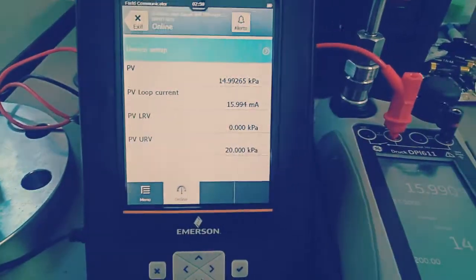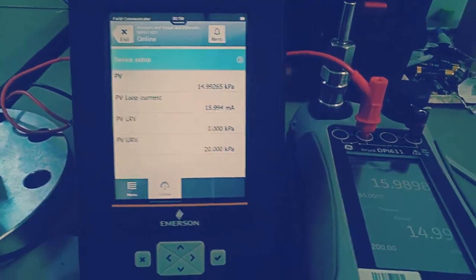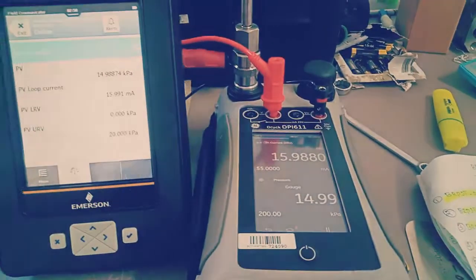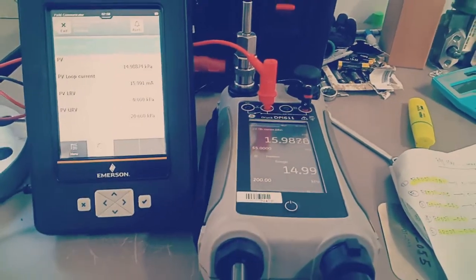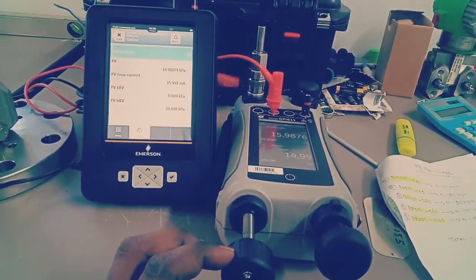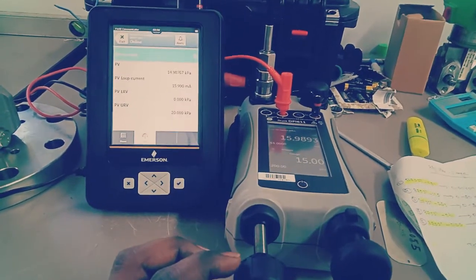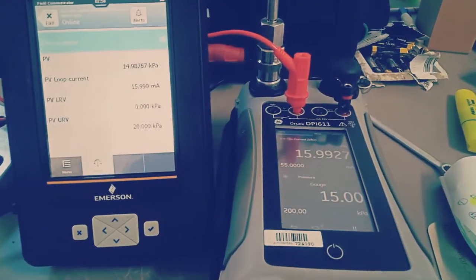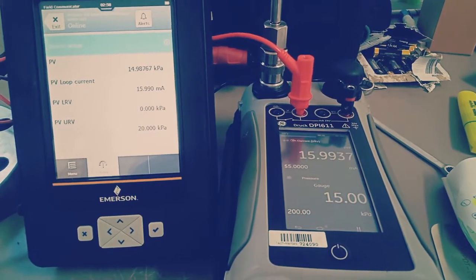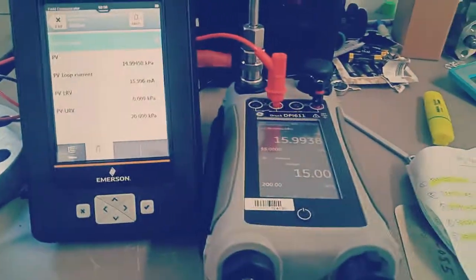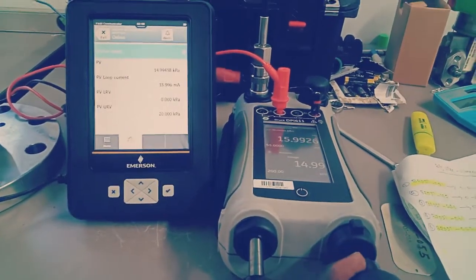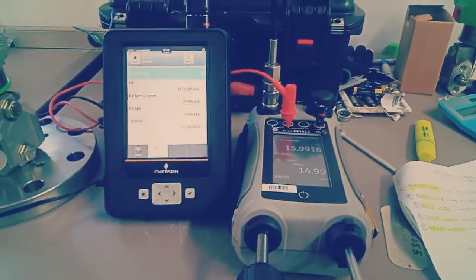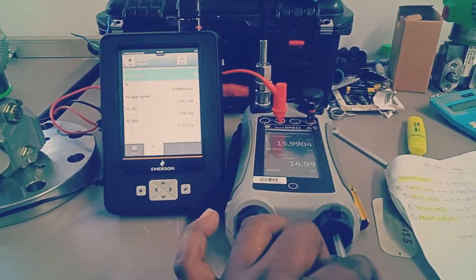It is acceptable according to error calculation and transmitter error limit. You can see it reads for 15 kilopascal, it reads almost 15.99. That's our 75 percent value, and I will move on to 20 kilopascal, just steadily rising to the 20 kilopascal value.